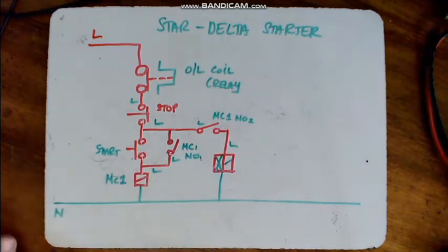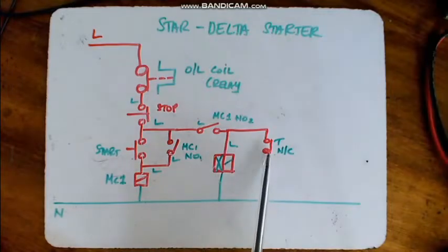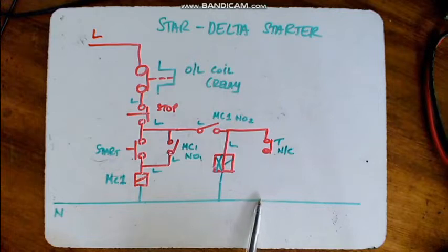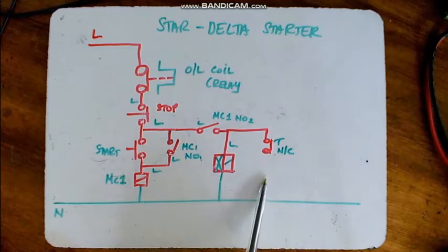Now remember, with your star delta motor starter, when the timer is activated, this switch must immediately start the timer, and must immediately start the star contactor. So this will be a normally closed switch, so that this contactor that controls the star connection will keep the motor running in star immediately.